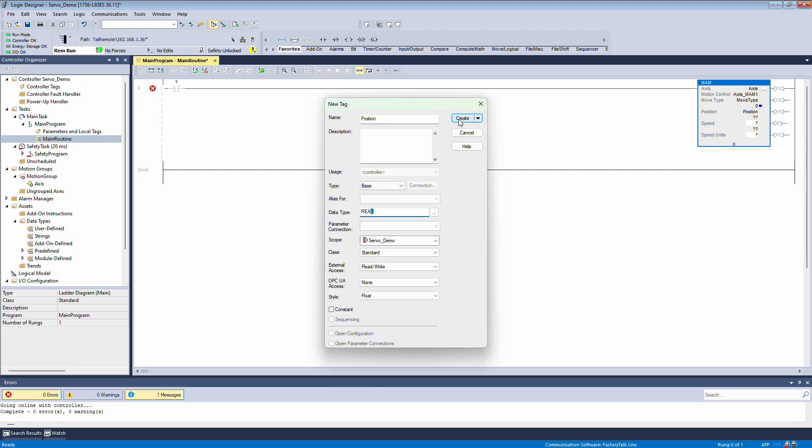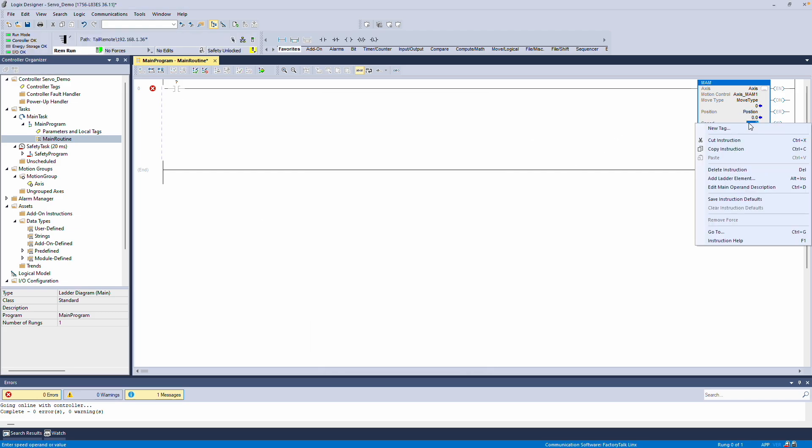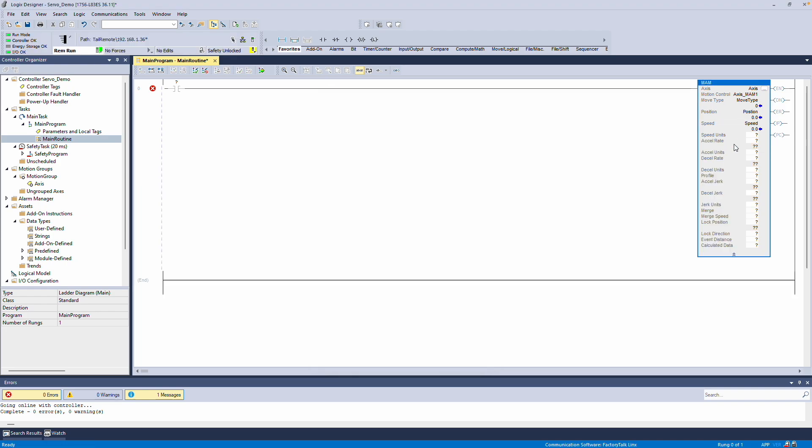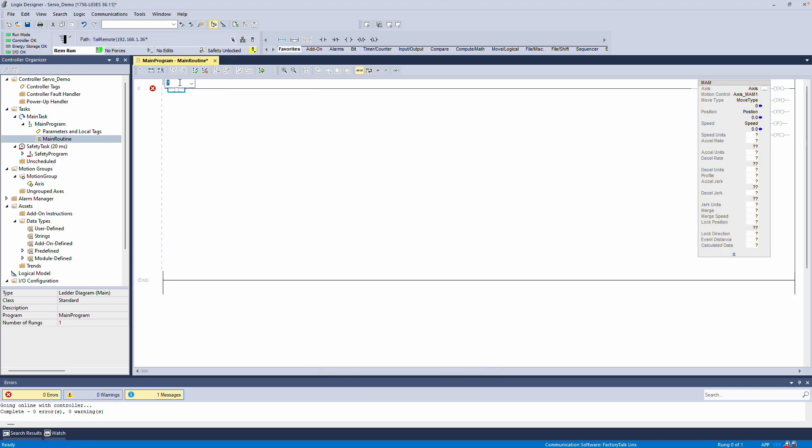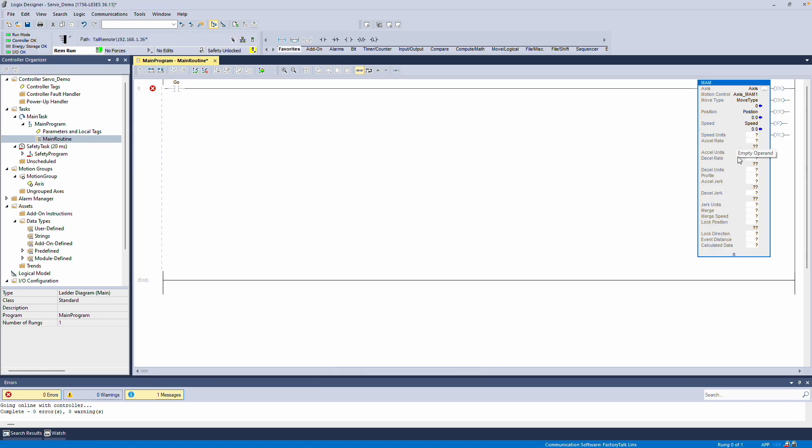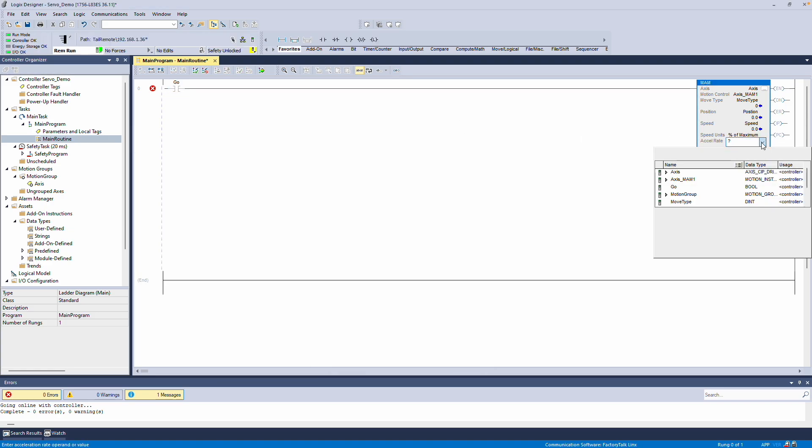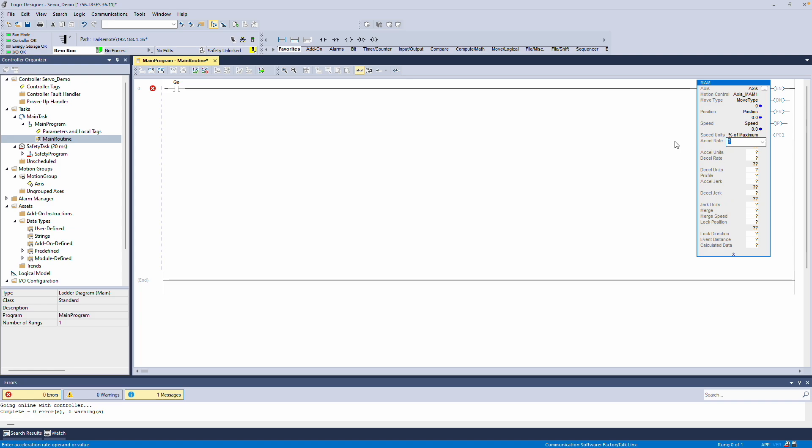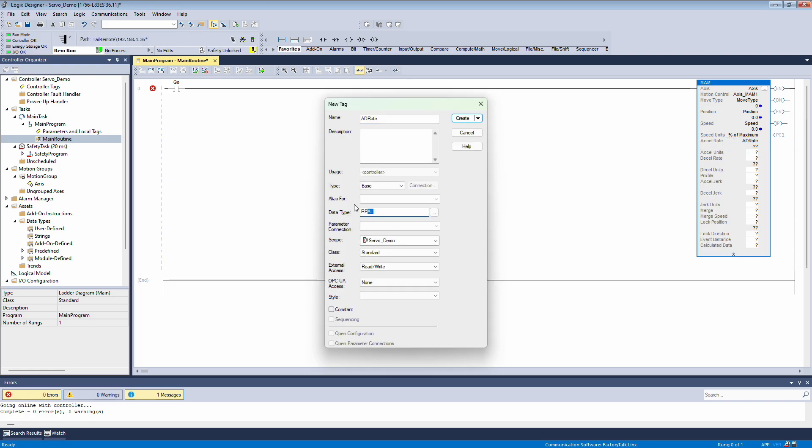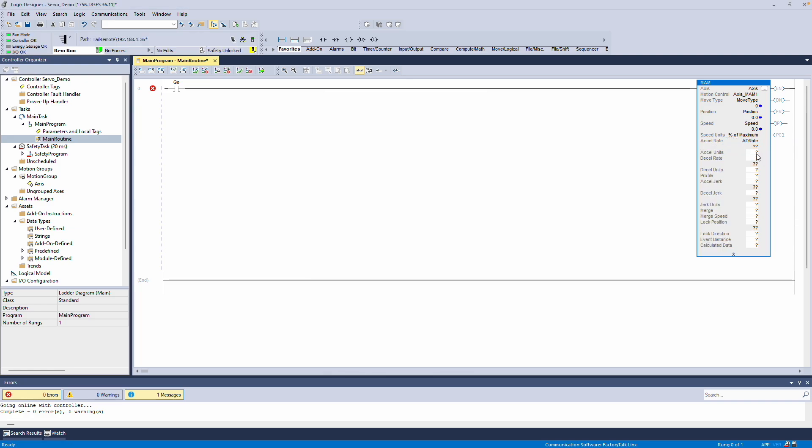The same applies to Speed, which I'll also declare as a real. Next, I'll add a Boolean variable called Go, which will be used for activation. For Speed Units, I'll select Percentage of Maximum. And for the Acceleration Rate, I'll declare another real variable named AD Rate, which I'll use for both Acceleration and Deceleration.